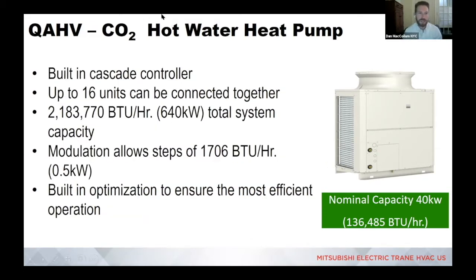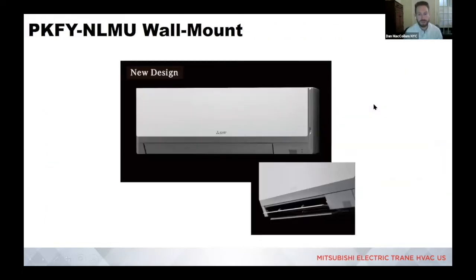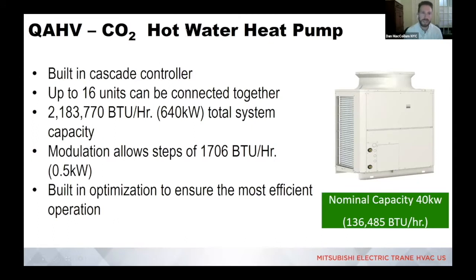These units, similar to the typical VRF outdoor units, are able to be interconnected on the controls side, and they can be cascaded together. So if you have a large heating demand for your building, you can connect as many as 16 of these units together in tandem to get you up above 2 million BTUs.